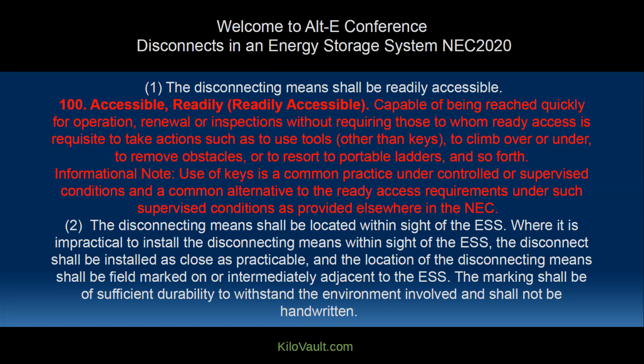A disconnect means shall be readily accessible. Readily accessible means it's going to be visible, and you don't have to be climbing over items. It's kind of hard when you have an installation in a customer's home and that energy storage room now becomes a storage room for all the unwanted items the customer has. So you want to make sure you have that area cleared. You don't want more heat being generated, or dust being generated, in that room. It should be easy to work on and easy to access, because it can take time to clean things out, and that makes a hazard if there is an arc fault while maintaining, servicing, or diagnosing equipment. You don't want to be tripping over items trying to get out of there or trying to access a disconnect.